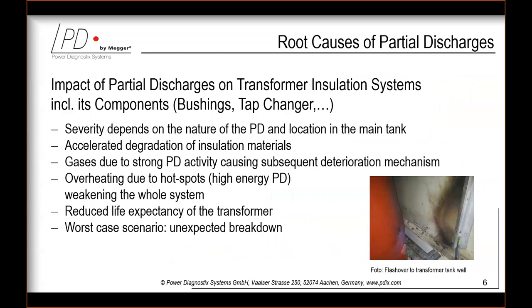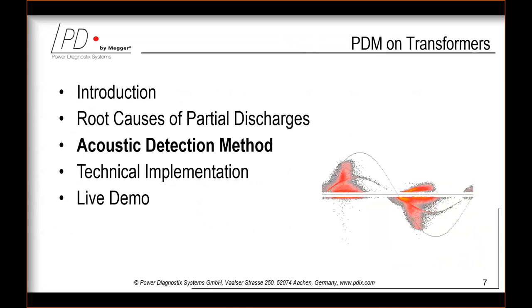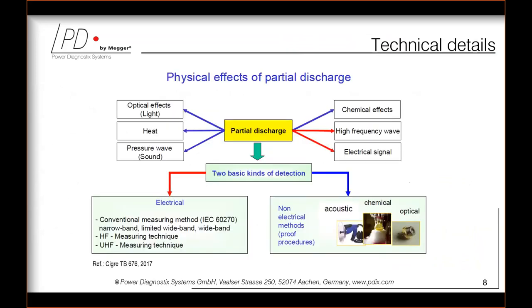The impact of partial discharges on transformer insulation systems — including components such as bushings and tap changers — depends on the severity and location. Effects include accelerated degradation of insulation materials, gassing causing subsequent deterioration, overheating from hot spots with high-energy PD, and a generally reduced life expectancy. The worst-case scenario is always an unexpected breakdown.